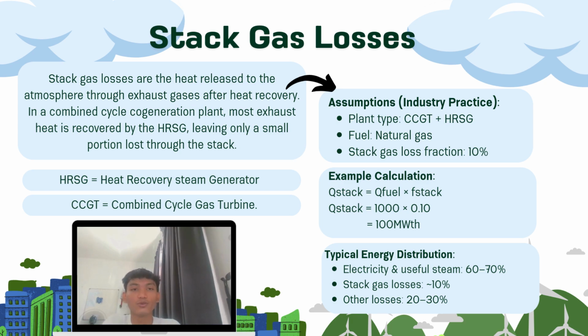So we are going to continue with the stack gas losses. Stack gas losses are the heat released to the atmosphere through the exhaust gas after the heat recovery. In a combined cycle cogeneration plant, most exhaust heat is recovered by the HRSG, which means the heat recovery steam generator, leaving only a small portion lost through the stack.